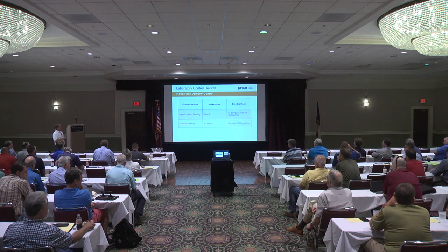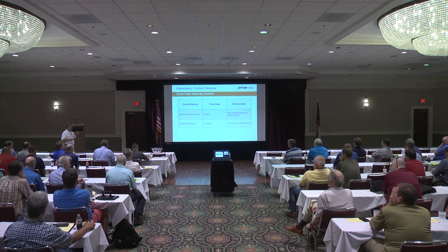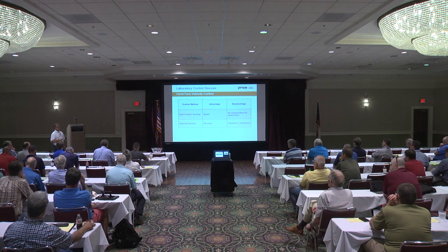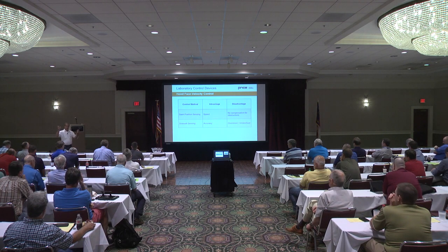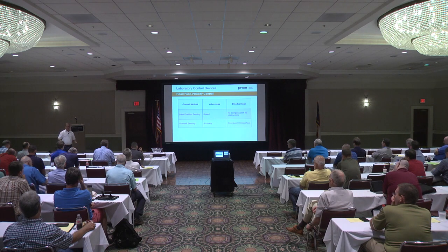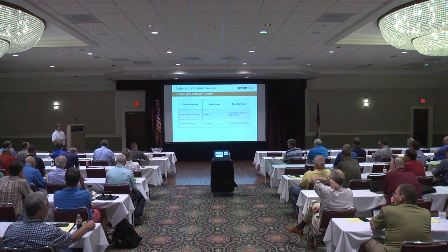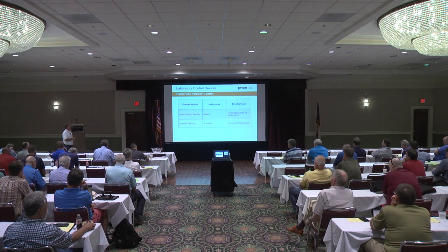Obstructions. With sidewall sensing, if you have an accurate enough sensor in the sidewall, then it'll do a good job of controlling an accurate airflow. But just like any control device where you're measuring airflow, you're going to have overshoots and undershoots. And in a fume hood, it may be open momentarily and then reclosed, so you're continually trying to catch and find the set point in a fume hood, unless you just leave it open.